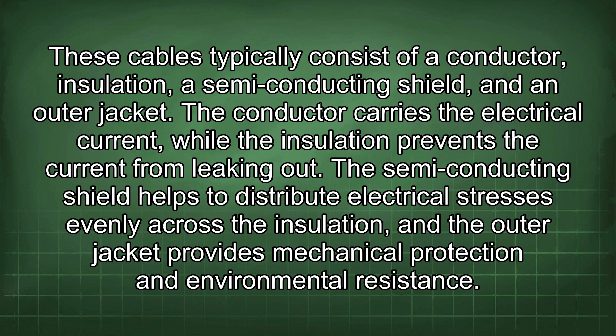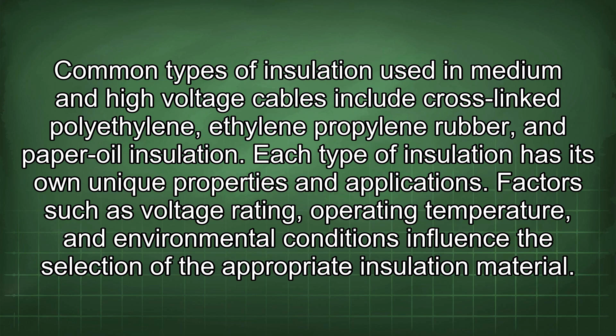Common types of insulation used in medium and high voltage cables include cross-linked polyethylene, ethylene propylene rubber, and paper oil insulation. Each type of insulation has its own unique properties and applications. Factors such as voltage rating, operating temperature, and environmental conditions influence the selection of the appropriate insulation material.